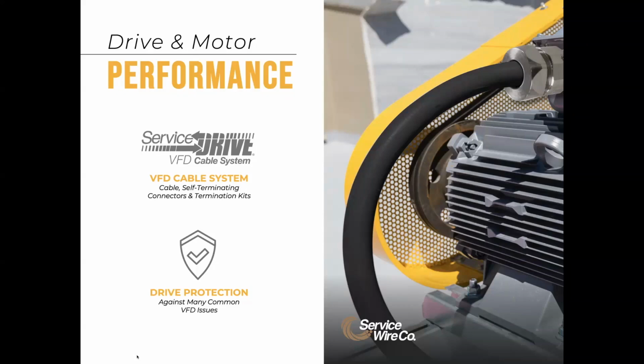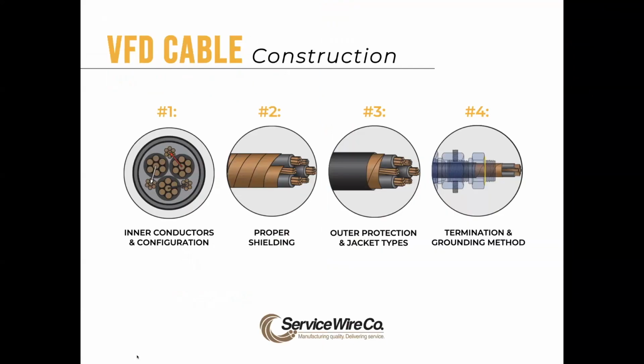This application would be better suited for cable with a thermoset outer jacket because over time the heat will drive out the plasticizers in the PVC jacket, making it brittle. ServiceWire's Service Drive VFD cable is the perfect fit for these types of applications. The cable is insulated with heat and moisture resistant XLPE and covered with a copper tape shield and overall CPE or low smoke zero halogen jacket.